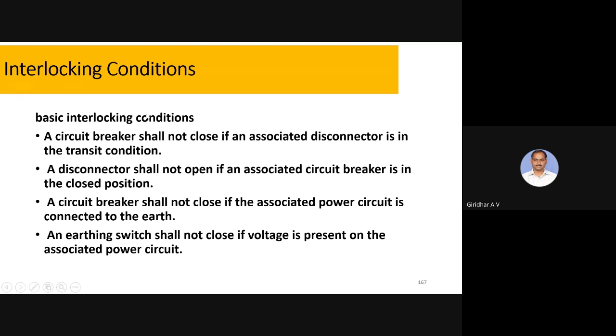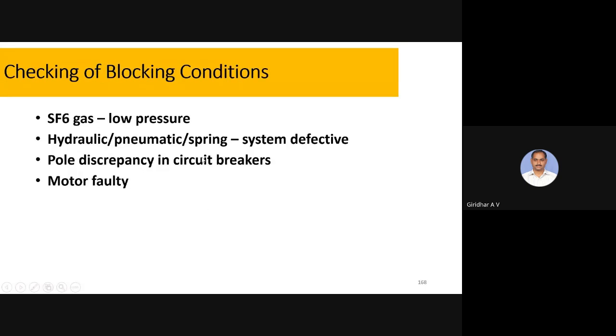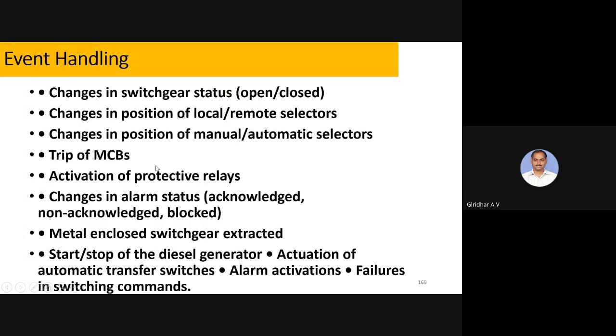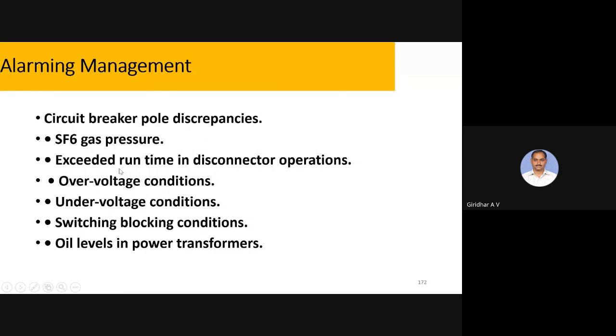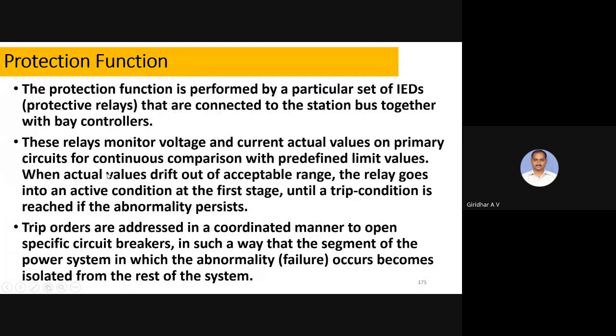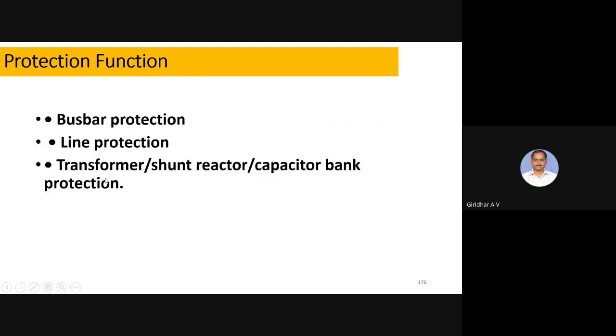So you can see in the interlocking conditions, the circuit breaker will not close if any associated disconnector is in transit condition. So like this, all things will be monitored. Suppose a disconnector shall not open if the associated circuit breaker is in closed position. Checking of blocking conditions: suppose there is any low pressure in the circuit breaker, where pneumatic operation is there, those things will be blocked and appropriate actions will be taken. So alarm management, everything will be done. Even from the IEDs, protections will be done.